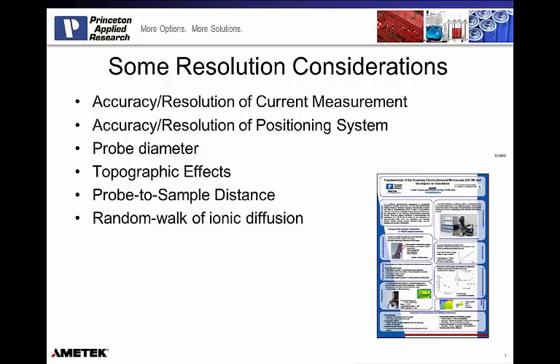But controlling that relates, there's an interplay to the topographic measurements above, and it's also an interplay with the probe to sample distance for the probe diameter, because as that diameter decreases in the probe, we need that probe to sample distance to get smaller, and then you have even more of a possibility of having topographic effects. So these all go hand in hand with each other, and a lot of thought has to happen to determine which one needs to be improved to improve the total resolution and accuracy of the experiment itself.